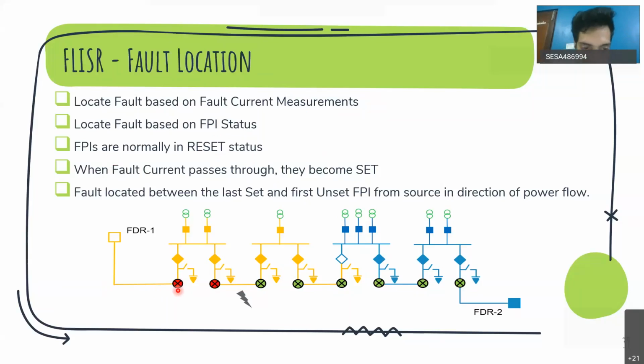For example, consider a fault in this section between these two RMUs. What happens immediately? Obviously, your feeder breaker will trip. But before the feeder breaker has tripped, some fault current was passing through this network. It is passing through this FPI this way, passing through this FPI, and it is stopping here. Like I told you, FPIs will get set when there is fault current.